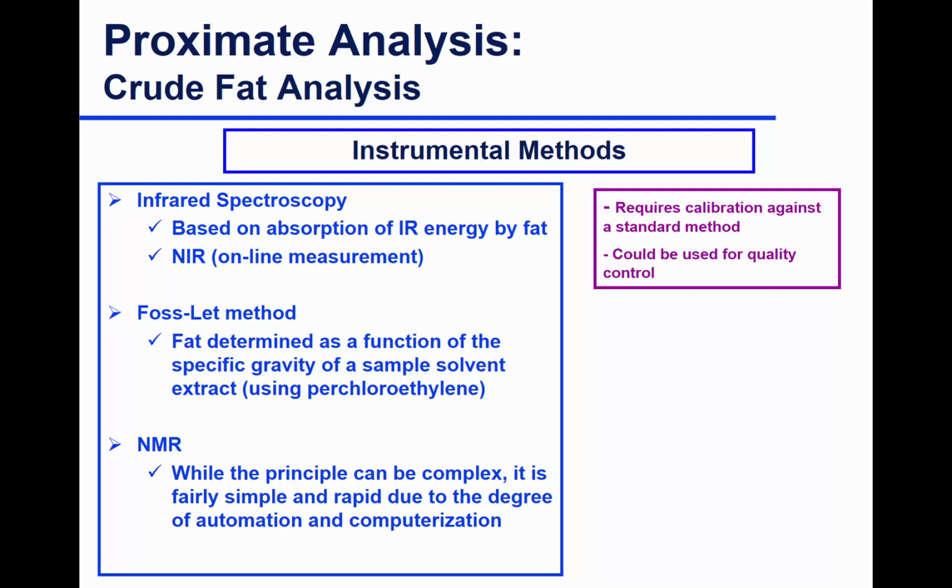And it's always calibrated against standard methods, against your Soxhlet or Mojonnier. So if you go to any analytical labs that have IR, they already have a room for the analytical methods. They have the Mojonnier, they have the Kjeldahl, they have the moisture oven and the furnace to standardize their IR, to calibrate their IR.